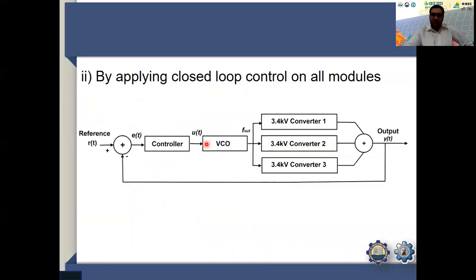So on the basis of this theory, we came up with this closed control loop on all modules. By changing the frequency of the gating signal of the inverter, we can control the output power. We will have a reference signal and the output signal, and their difference will produce an error signal that will be passed through the controller. The controller will generate a signal that will be fed to a voltage controlled oscillator. Based on the magnitude of this output voltage generated by the controller, the VCO will produce a frequency either greater or less than the resonance frequency, and that will be fed to these converters, and the output voltage will be controlled.